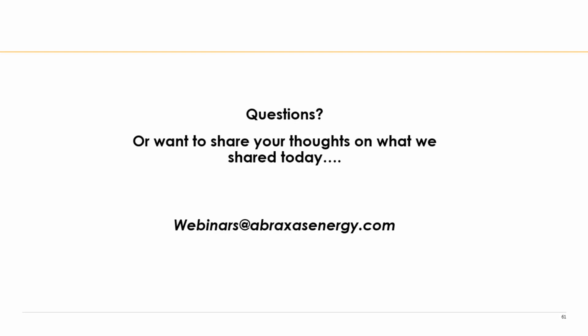Okay, here's one. The enVerid technical literature lists 2 different regeneration cycles per day. How many total times per day are the regenerative heaters running? Yep, typically it's once a day for about an hour. It can be more, especially if there's full occupancy for the entire runtime. And the unit itself is able to figure out if cartridges are becoming saturated, but typically we're programming the system for once a day, worst case scenario, regeneration, and we can do a partial regeneration in the middle of the day or at the end of the day if the building was overly occupied.